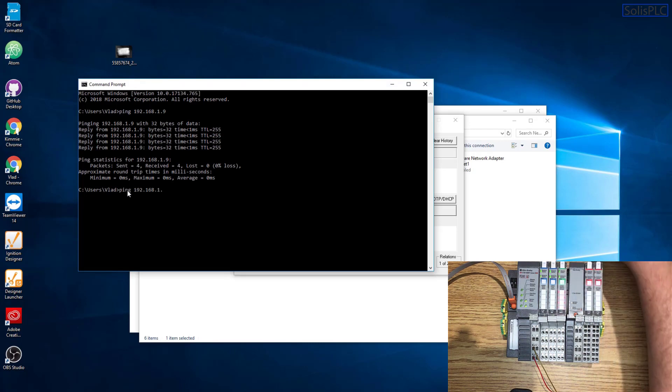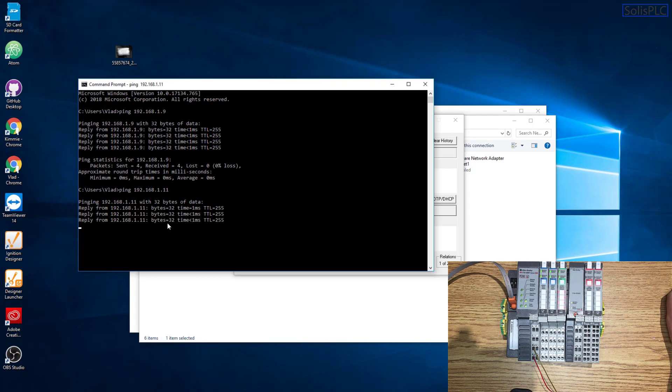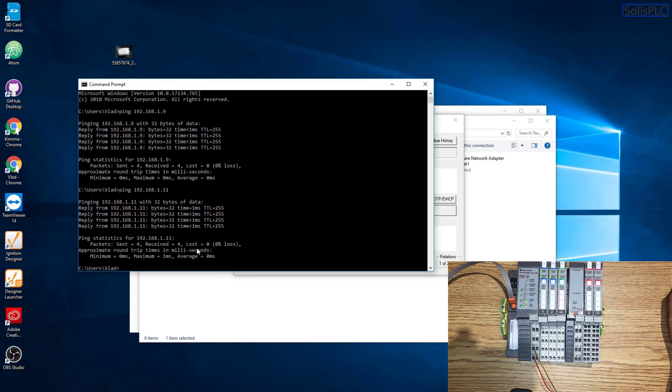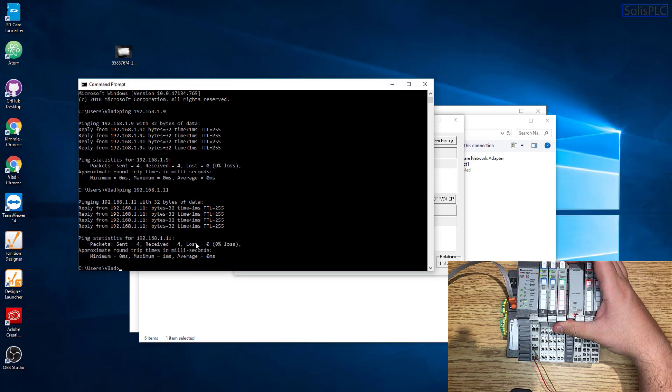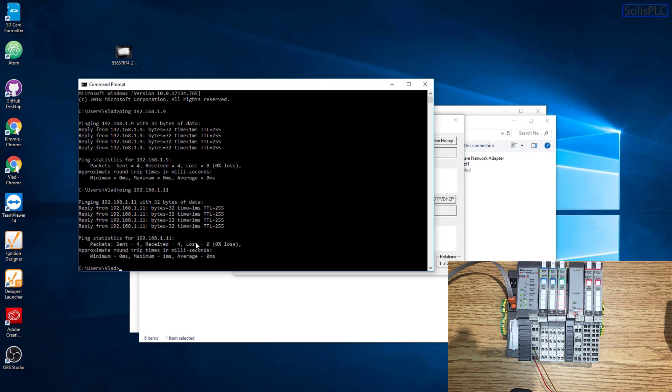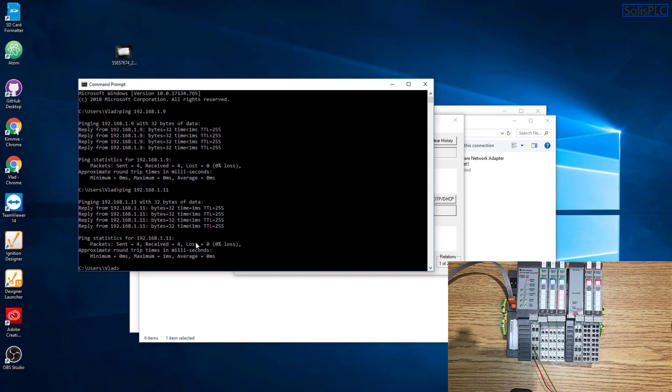Let's just ping that specific IP address and see if it took. So 0.11, as you can see, is the new IP address which has been stored on the module. And it is now set to 0.11. I am going to change it to 0.9 again, just because that's the IP address I had assigned to it for some other purposes. But this is the way to effectively set this IP address without having the need to use BootP or DHCP and allow, like I said, people on the floor to be able to do quick swap outs without the need of laptops or any other softwares.